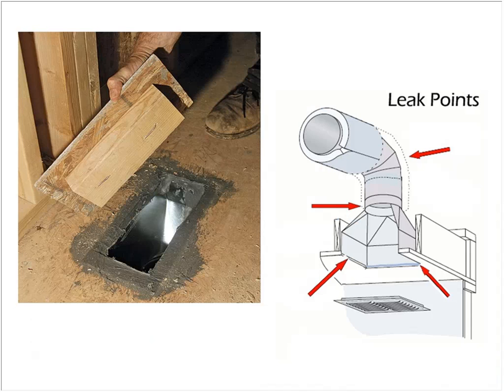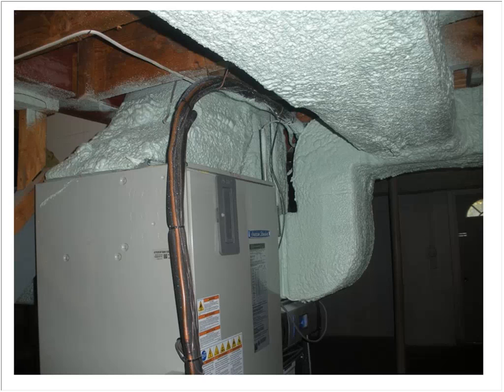So a good job of air sealing is important, and I'm happy to say that in the 30 years that I've been doing home performance inspections, it is getting to be more and more commonplace to see really good air sealing detail by the mechanical contractors. So it's a good idea to have the conversation with your contractors to make sure that your home doesn't have problems if testing is required, or performance problems if in fact the occupants enter a home that hasn't been tested for duct leakage, just to ensure that they've got the conditioned air going where it's needed.